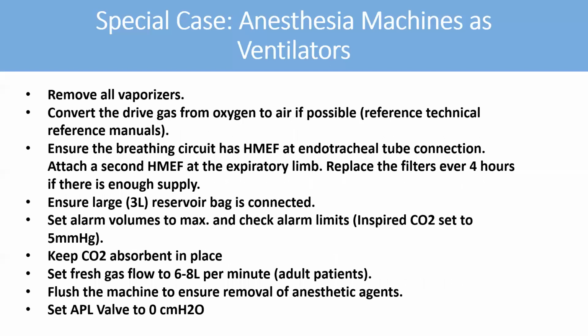So how do you do it? Remove the vaporizer. You're not going to use a vaporizer. Convert the driving gas from oxygen to air. Basically you can combine oxygen and air. Refer to the technical reference in your manual. Make sure you're using an HME filter at the endotracheal tube connection. Attach a second HME filter or HEPA filter and replace the filter every 4 hours, depending on the condition. And ensure a 3-liter reservoir bag is connected.